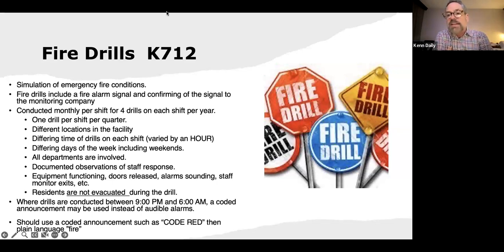That signal is being sent and received within no more than 90 seconds. So you have to get the time your pull station was pulled or initiated and the time they received it, and document the fact that that has been done, all within 90 seconds. During a regular fire drill, that's fine. And then if you do a coded announcement drill in the middle of the night, you would do it the next morning or the next day; you could test the fire alarm.